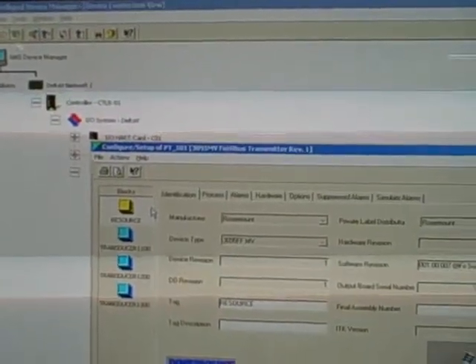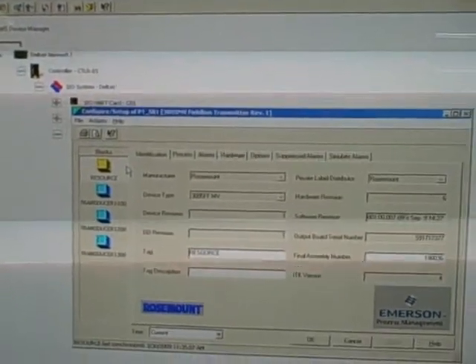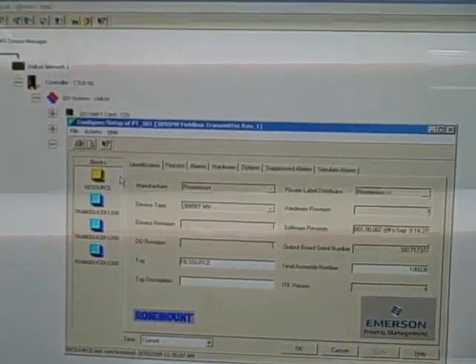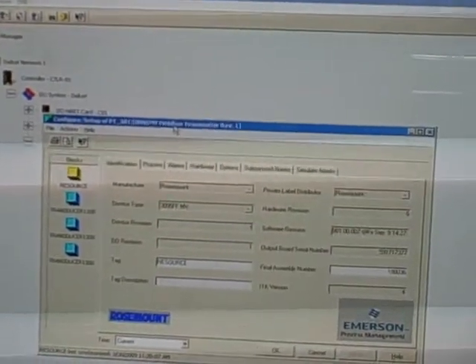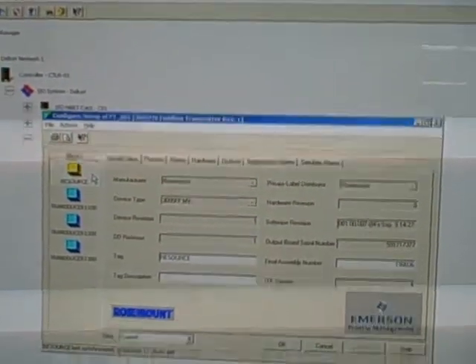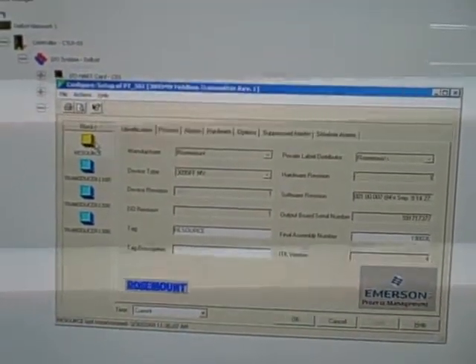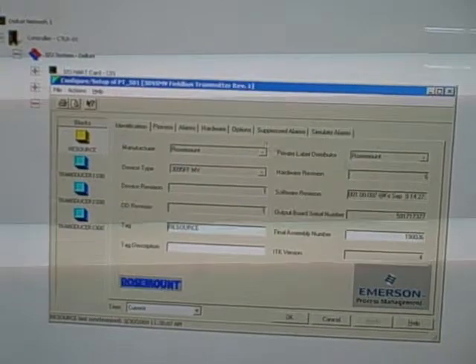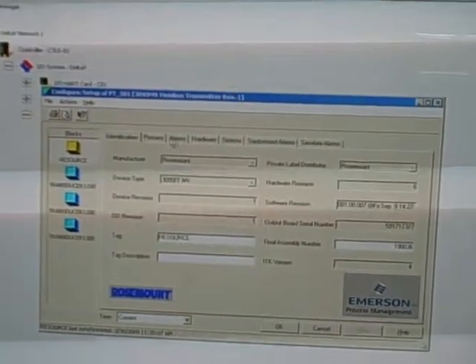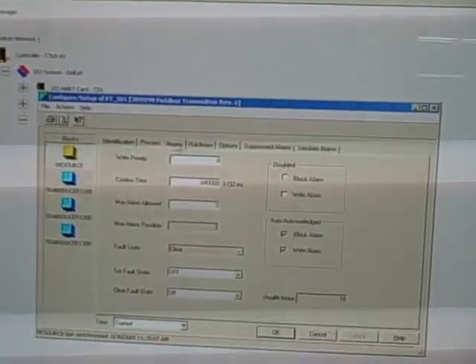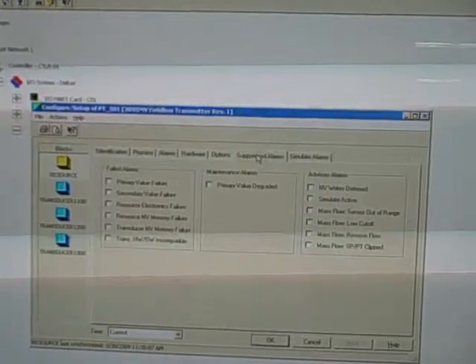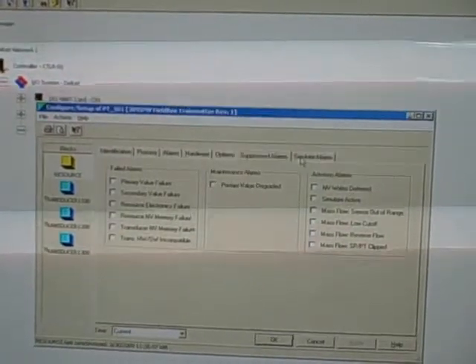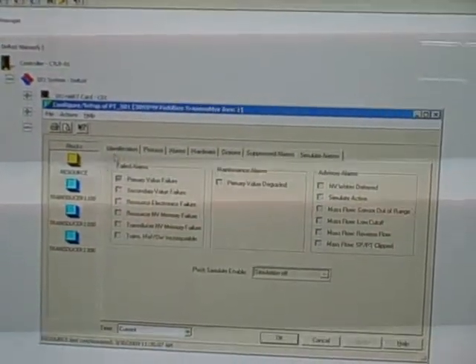This is an Emerson Rosemount 3095 multivariable transmitter. The first block that comes up in this transmitter as we interrogate it through AMS is the resource block, describing what the transmitter is doing, alarms it may have, options to suppress or enable alarms, and we can simulate alarms here.